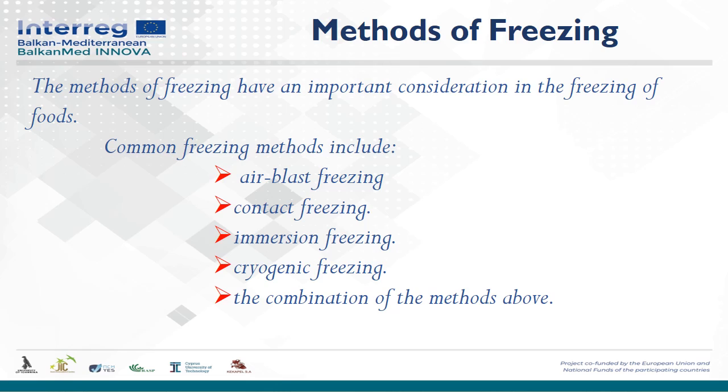The other method of freezing is through the use of large fans in cooling rooms to increase the convection heat transfer coefficient and, of course, the freezing rate. These freezing methods are still being used for many food products, but nowadays these methods are being replaced by conveyor type freezers, as they allow automatization of the process and lower operating costs.